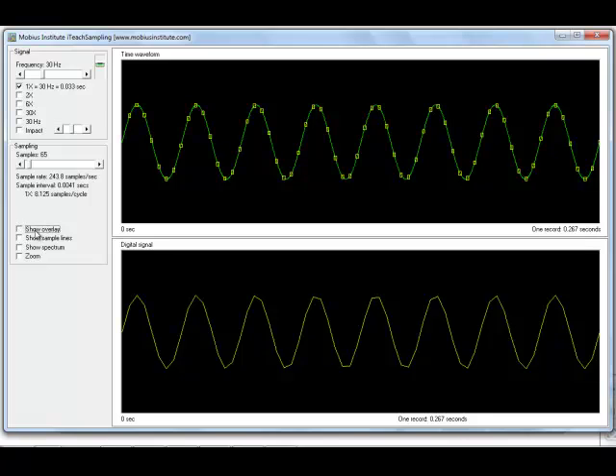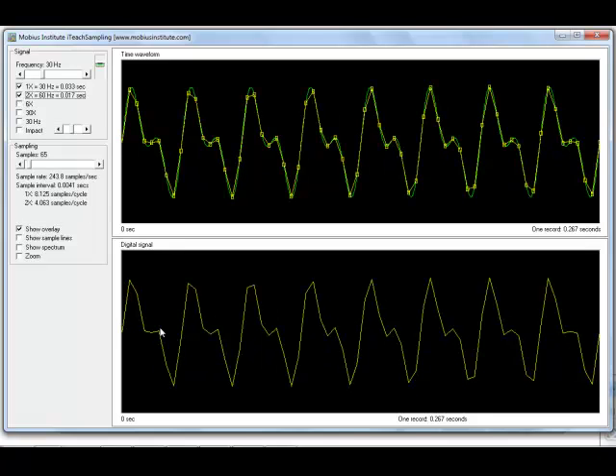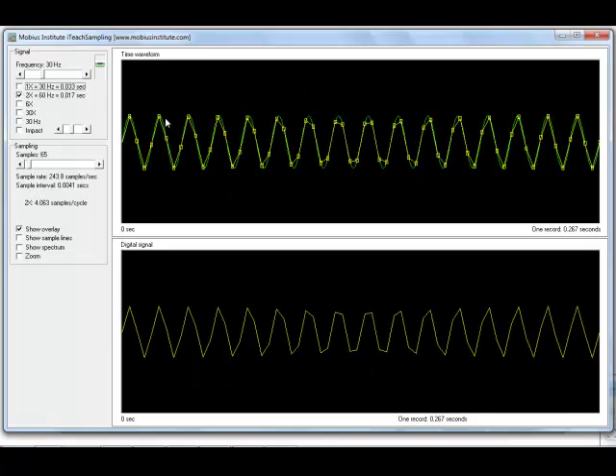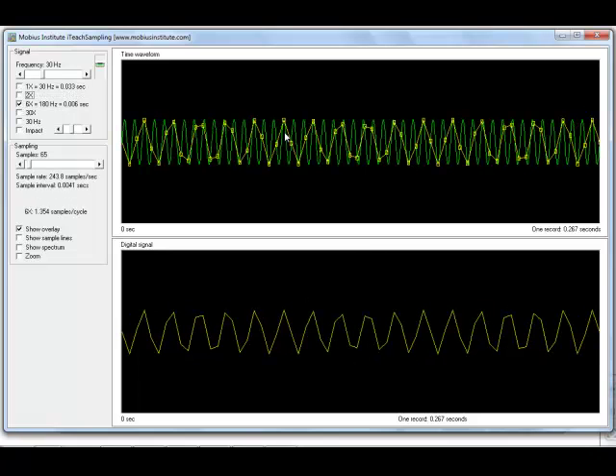If I turn off the overlay, you can see the green one more clearly. Of course, if we then had higher frequency vibration, you can see the samples are high enough that even with a higher frequency component, there's just the 2x vibration, and then 6x. Now we're not sampling it high enough. The design of the analyzer and the way your software works is to always make sure we're sampling more than 2x as high — in fact, 2.56 samples per cycle of the highest frequency we're interested in.